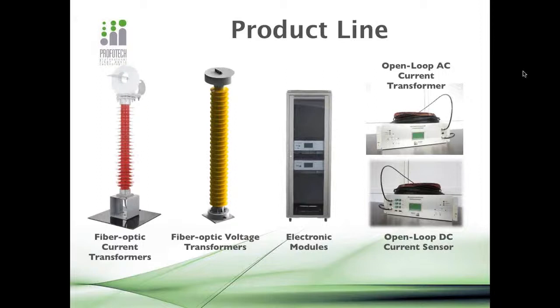So it's time to go to fiber optic instrument transformers produced by the company. There's a series of products. The product line consists of two types of high voltage sensors, and then several types of so-called open loop sensors. So the fiber optic current transformer consists of, you can see it to the left with the red column, the red isolator.